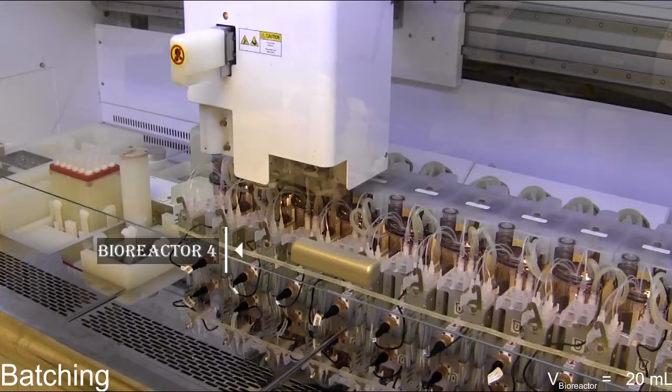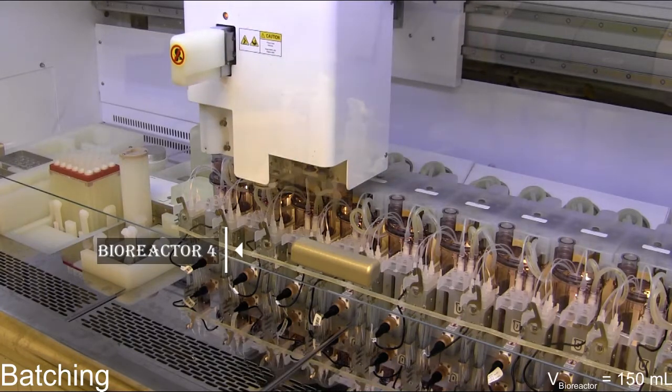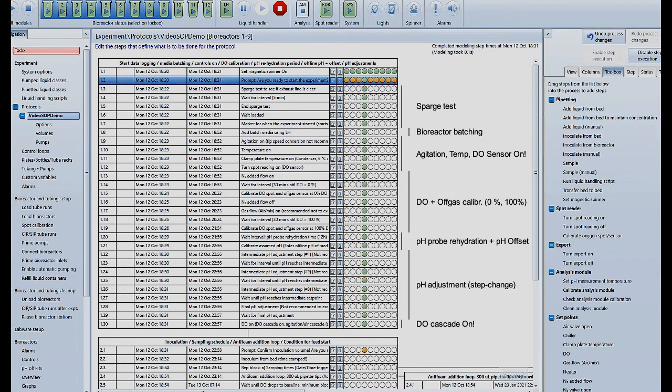Once the reactor volume is equal to the target, in this case 150 milliliters, the batching is over and the process script moves on to the next tasks. Bioreactor 4 is now ready for inoculation.